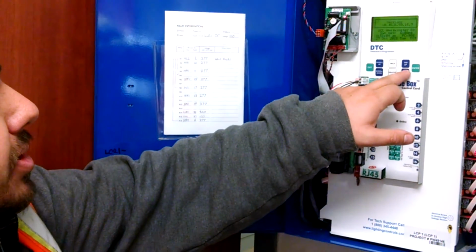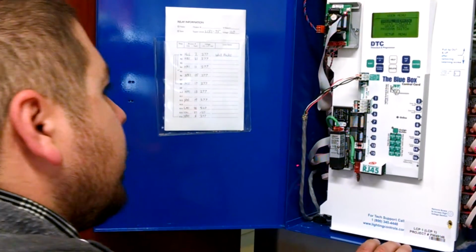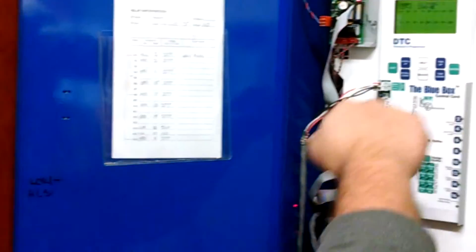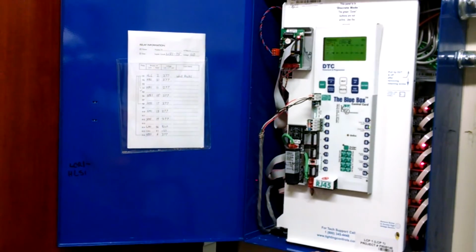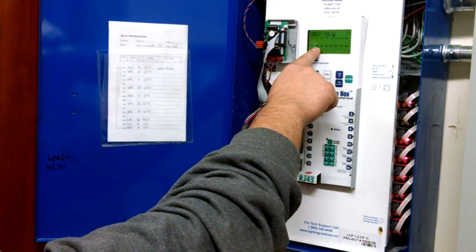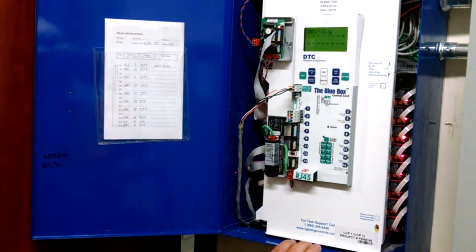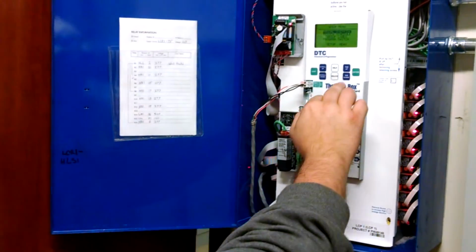Okay. If we press the tab button to get into the user menu, we have another option for manually overriding relays. If we go into manual override, press tab to go to the load, scroll up to the load we want to override, press enter, the relay clicks, the little light turns on, and you see that turns into a square. Square means lights on, dash means lights off. Push it again, light turns on. So that's another option to manually override your lights.